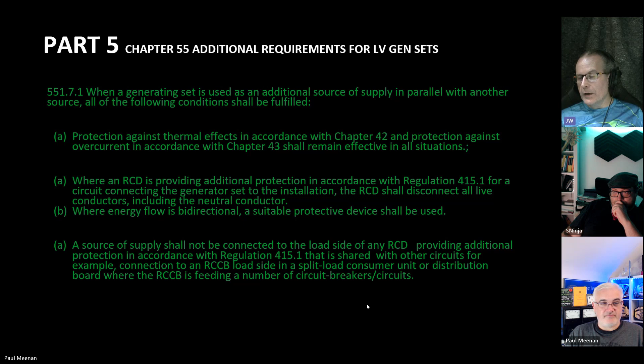The main problem with this is that if you've got that arrangement where you've got, say, 6 circuits, one of which is the solar, and it's all on the same thing, the RCD trips, but it doesn't disconnect until the inverter shuts down, which, depending on the type, could be many seconds rather than milliseconds. So 4 or 5 seconds later, it might shut off, and for that time, all your other circuits are still powered. So definitely not something you want.